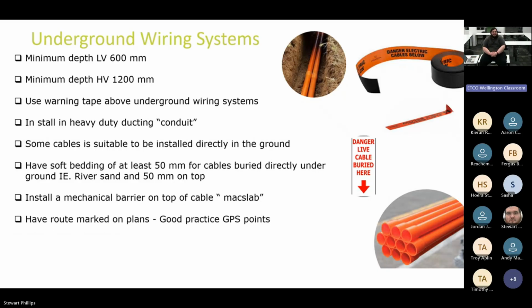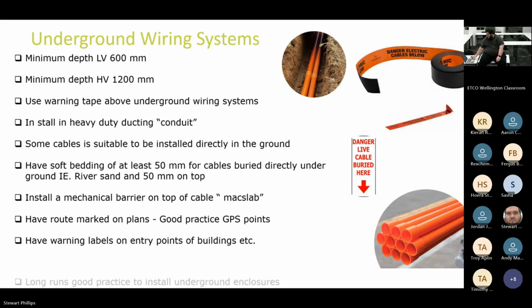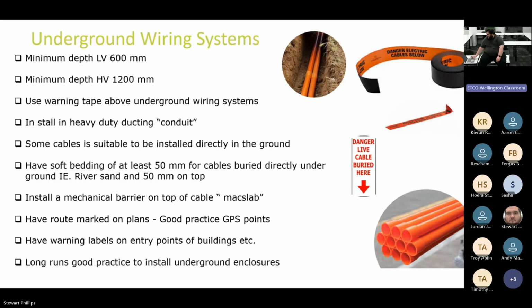Have route marked on plans, so good practice, GPS points. Warning labels on entry points of buildings. So that's that white danger live cable buried here. We need to install that where the cable enters the building. Long runs, a good practice to install underground enclosures. Again, good practice, not 100% necessary. Does make pulling them through a lot easier.